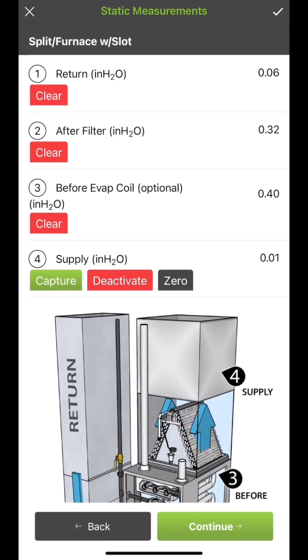And now here we are. We see that we got 0.1. We re-zero our manometer, and we are zeroed. And then we go ahead and install it in the next spot just to make sure everything is going. And then for whatever reason on the supply side, it always takes a little longer. So we got to give it plenty of time to settle out here. And once we're happy that it's settled, we know it is what it is.